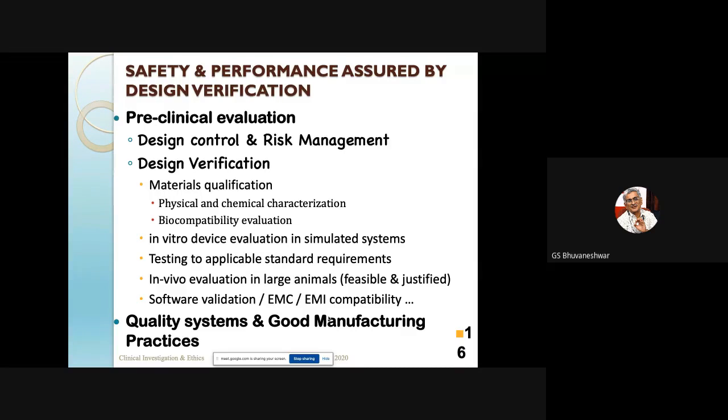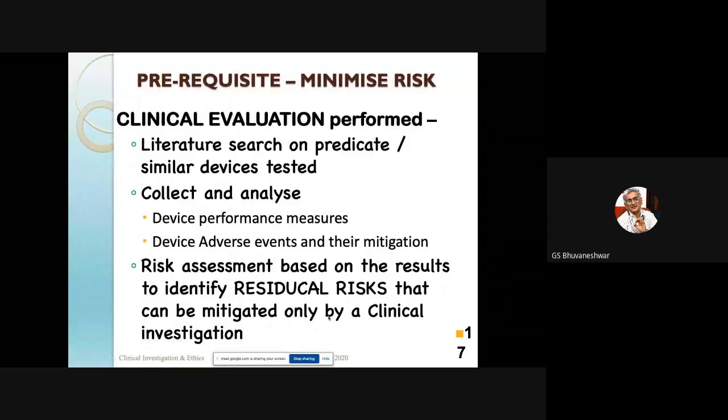So in a sense, you need to do a little bit like a pilot production before you can get into a good clinical investigation study. As I said, the clinical evaluation report has to be carried out. This is ideal because it gives you a lot of information on predicates of similar devices tested, collect and analyze the device performance and measures.